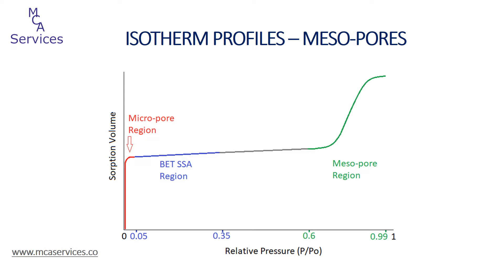The isotherm starts to curve upwards at around 0.6 relative pressure as the pores start to fill with adsorbate. Since this portion represents a mesoporous material, the pores will be completely filled with adsorbate as saturation is approached — that is, relative pressure close to one — and because of that we observe a horizontal region towards the end of the isotherm called the Gurvitch plateau.